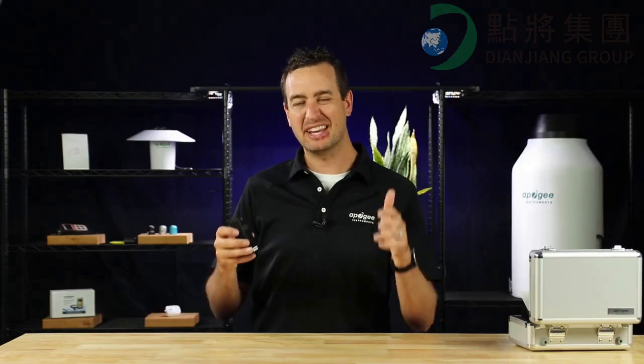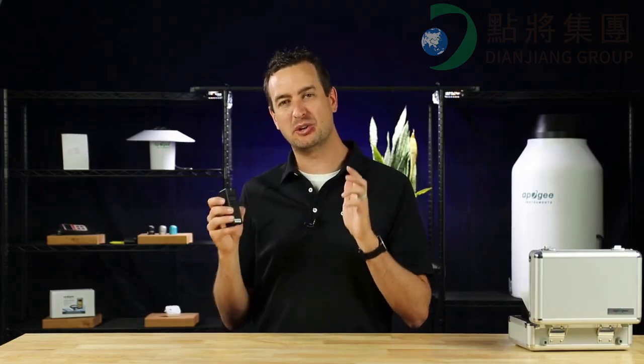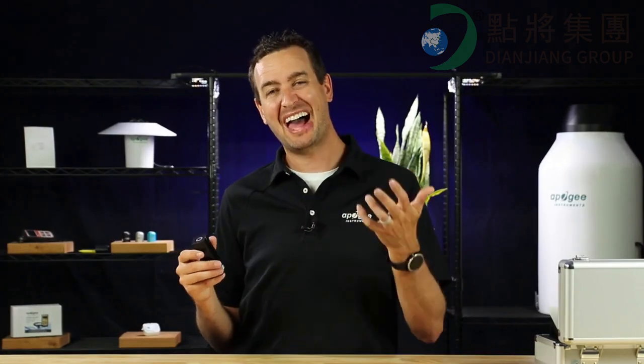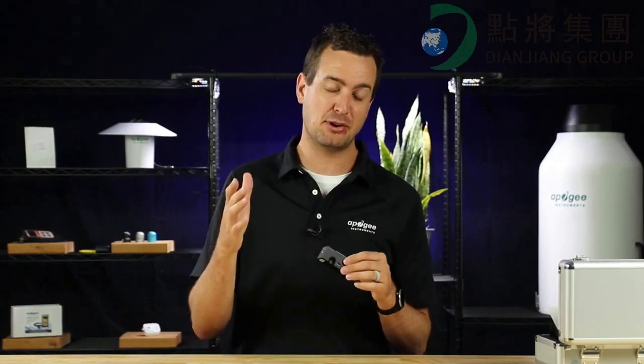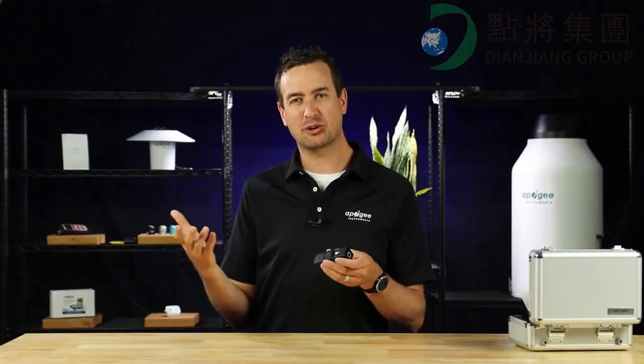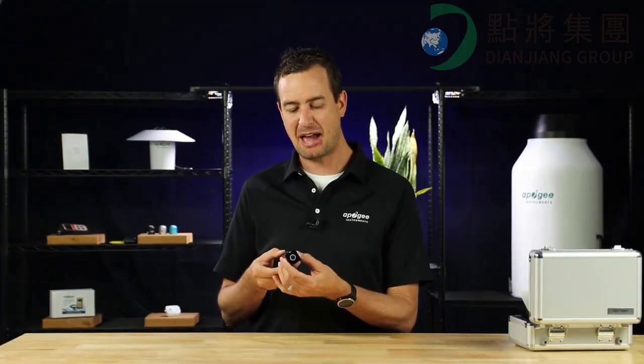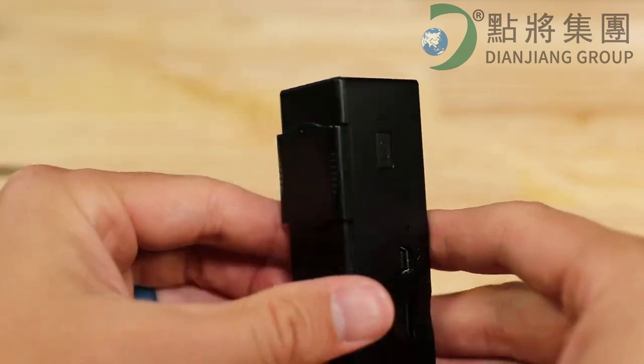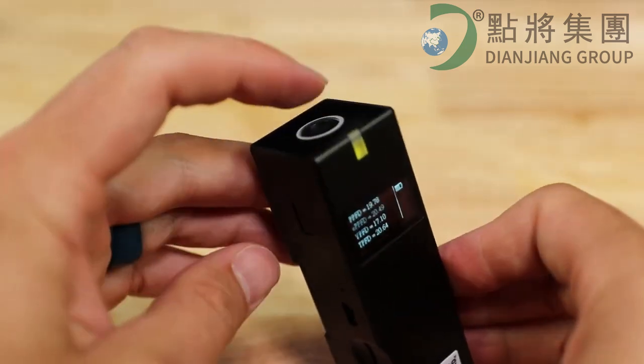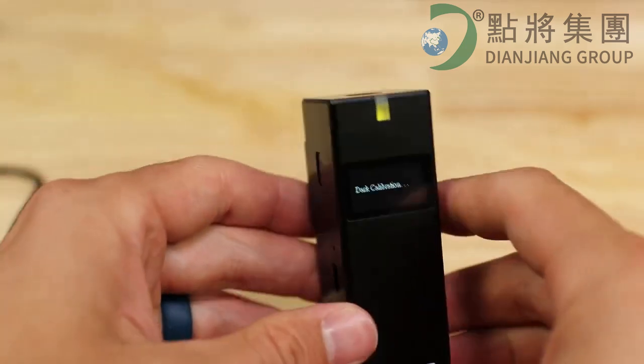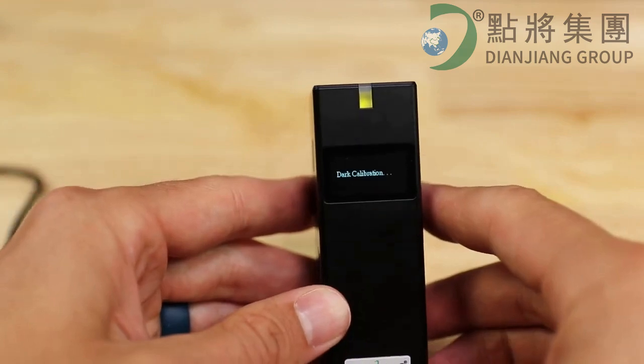For a spectroradiometer, it's very important to make sure that you do a dark calibration. To ensure the highest accuracy of measurements, make sure you do it often, especially when you change environments such as temperature or humidity. To perform a manual calibration, with the device powered on, close the shutter, and then press the measurement button, and it'll perform a dark calibration. Once that's been done, it's ready to begin taking measurements again.